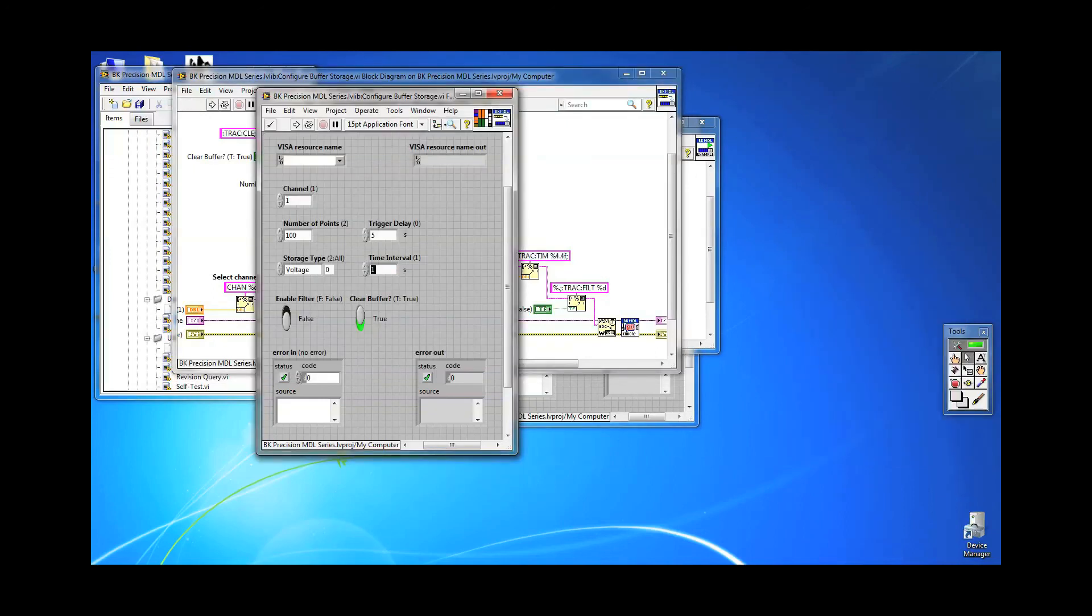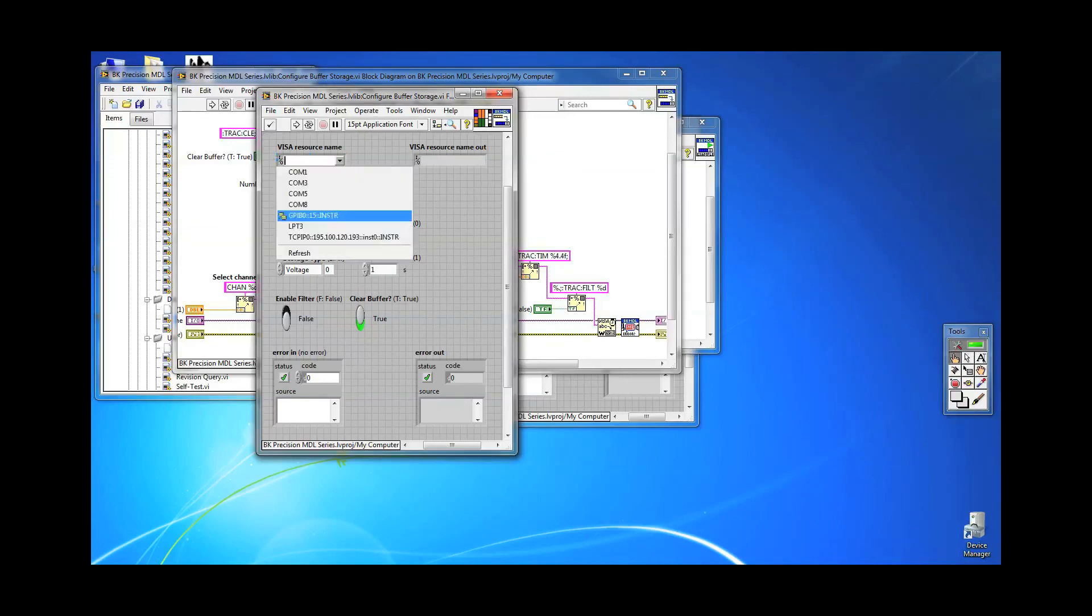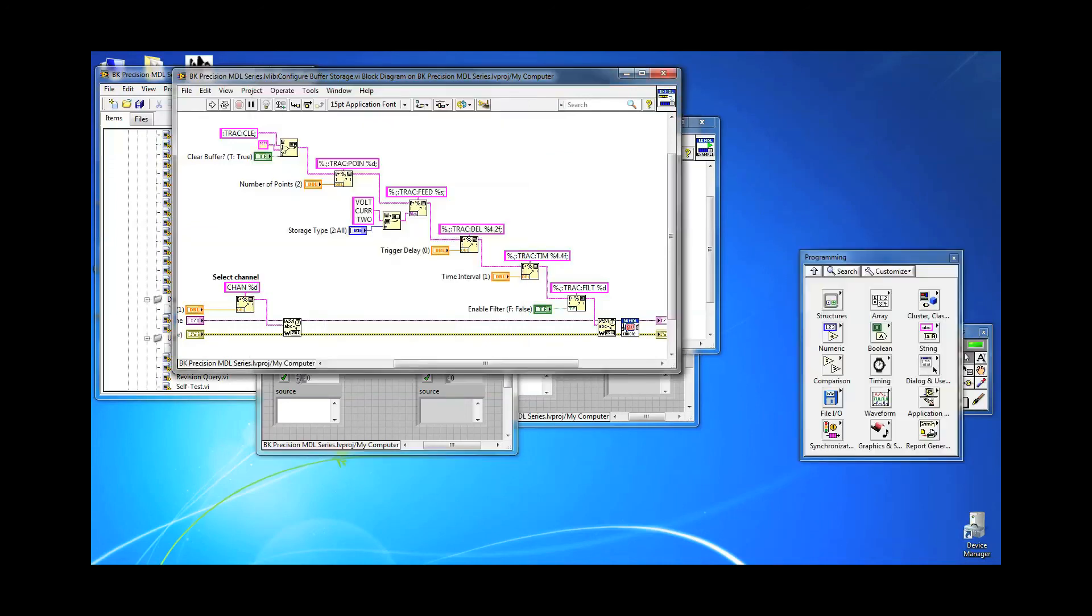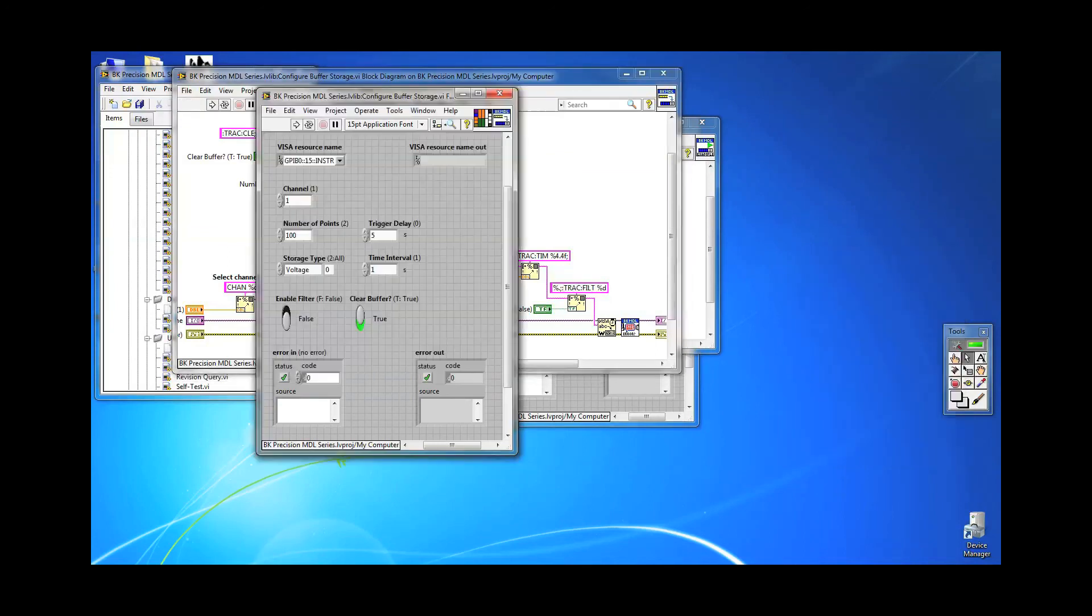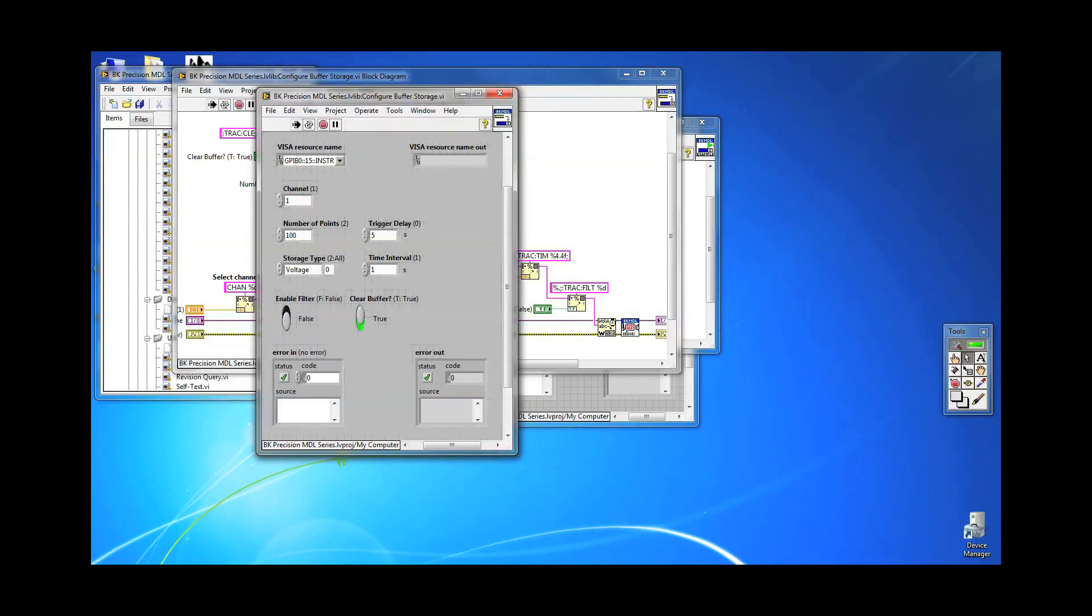The last parameter we can configure for the buffer storage operation setup is filtering. You can enable or disable filtering of the readings captured into the buffer with TRAC:FILT command. I will leave it disabled by sending TRAC:FILT 0. Before we can send a trigger, we need to send TRAC:FEED:CONT NEXT command, which configures the load to a wait for trigger status.